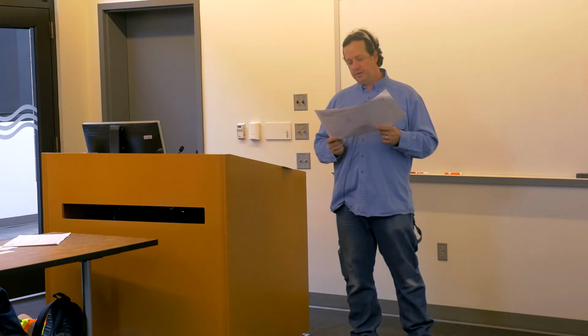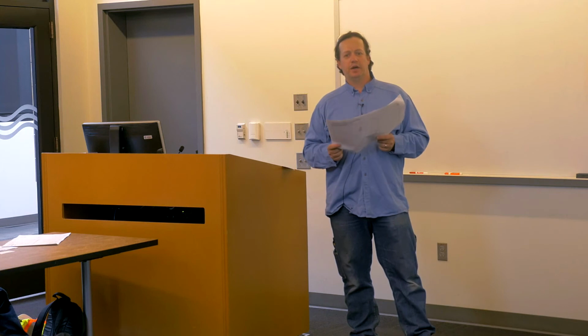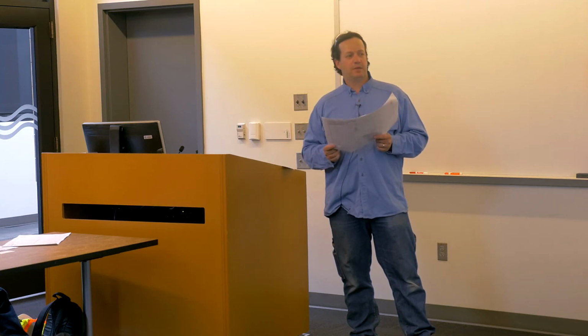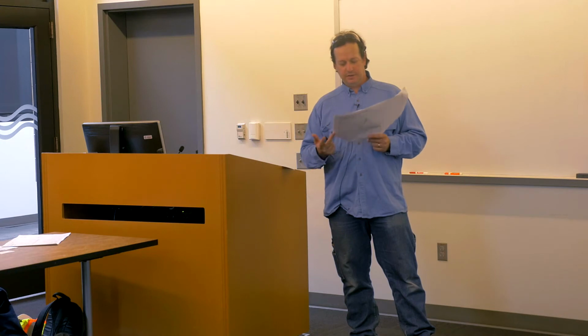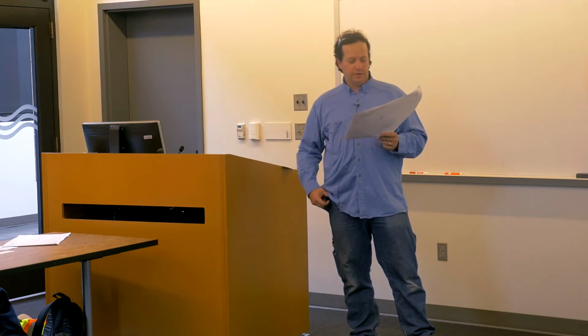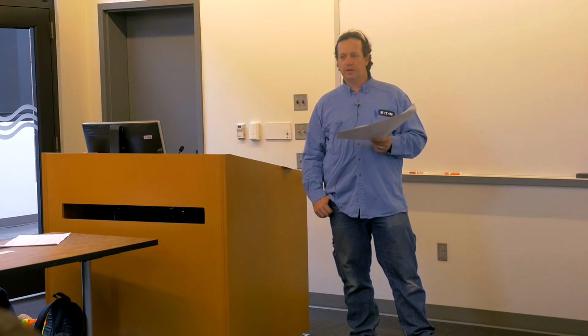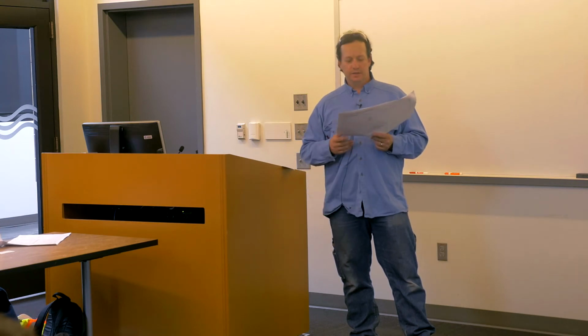So yeah, there's not a whole lot of components in this gear. You have 4 switches in the 5 sections. Your meter is actually powered off of your PT, so your meter won't be on unless you actually have power, the switchgear energized. If that's something later you guys decide you want to change, there's definitely workarounds, but it would require you bringing control power over to it.